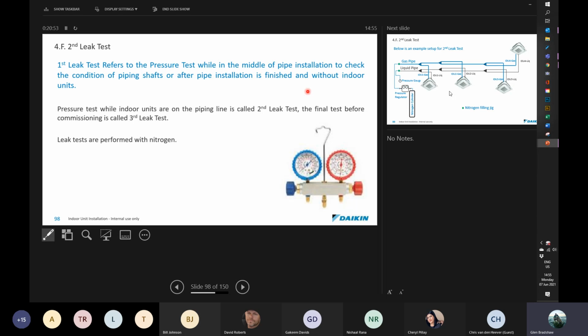It's very important. One of the things that we try and encourage the technicians to do is to do a number of pressure tests on a site. Pressure test your main piping separately. Pressure test your indoor units separately. If you've got many different floors, try and pressure test each floor individually before you connect the system up as a whole. This allows you that if you have a leak in the system, you can identify it to a smaller area and it takes less time to find.